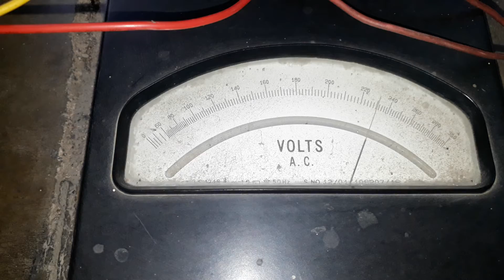The supply is switched on now. It is still not showing anything because I have not increased it. I have to set the voltage of the auto transformer at the desired value. You have to set the voltage according to the rating of the winding. The rating of that side of the transformer winding, wherein we have placed all these equipments, is 230 volt. So we have to set the voltage at 230 volts. Now I am increasing the supply from the auto transformer and I will set it at exactly 230. So it is now exactly at 230 volts.